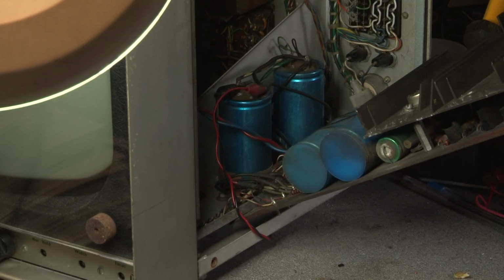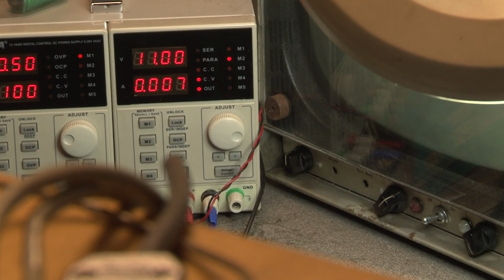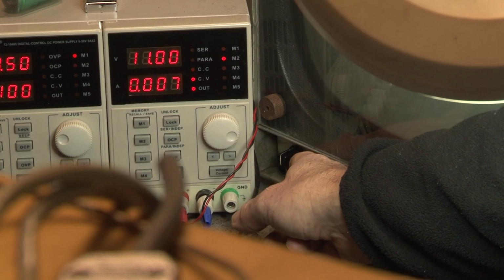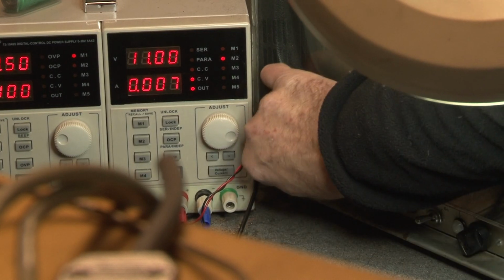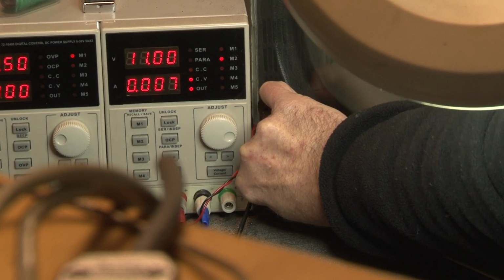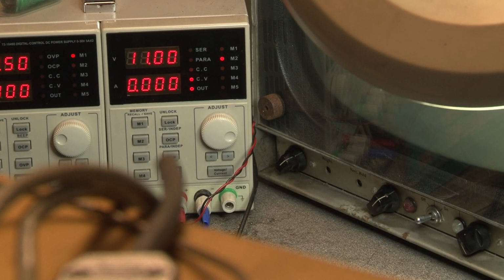So our 7 milliamps is actually coming from the relays here. So if I select remote by putting to that position, miraculously both relays open, and because there's no remote control plug in situ, and there's no video relay operating, there's no leakage current now.